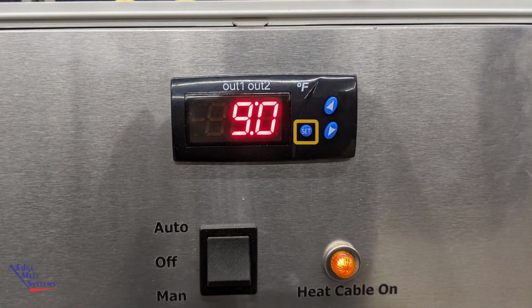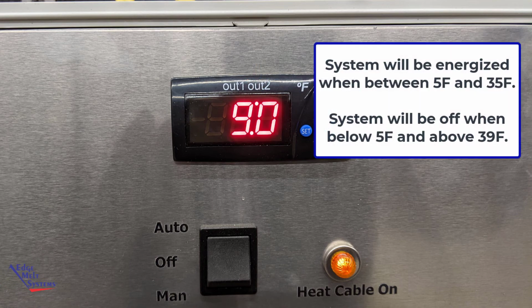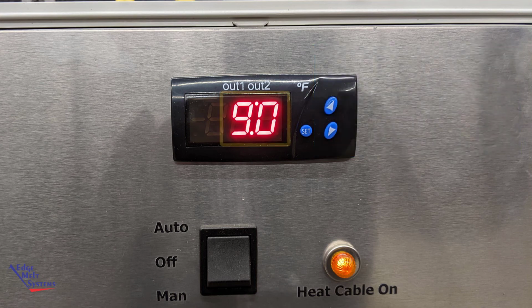Hit set once again, and a value of 9 degrees will display with a dot under the out 2. This is the second set value. That's the temperature at which when it rises back above 9 degrees, the heat cables will be energized. When it falls below 5 degrees, the heat cables will be de-energized. This means that the heat cables will essentially be on in a window between 35 and 5. When this 9 degrees is flashing, you'll be able to arrow up and arrow down, adjusting that value as well. Please bear in mind the 4-degree hysteresis.